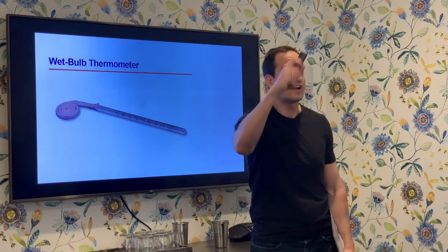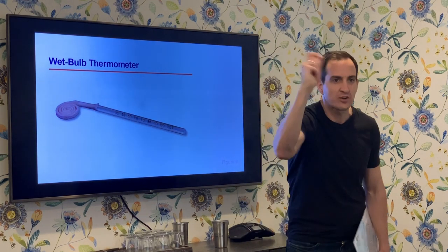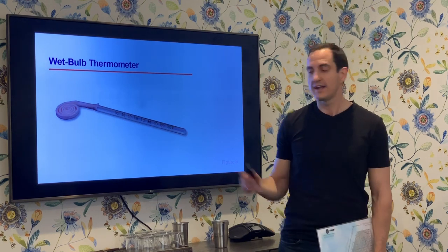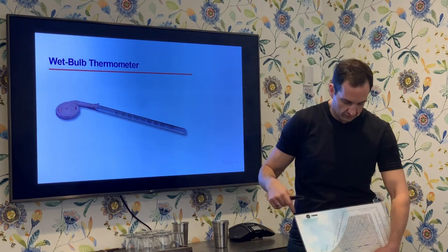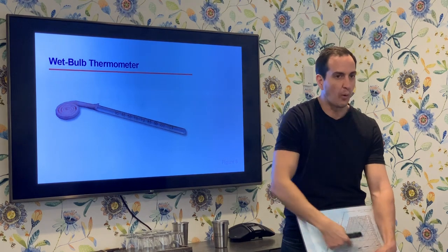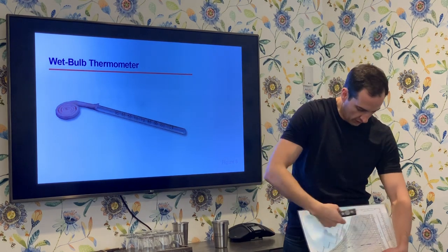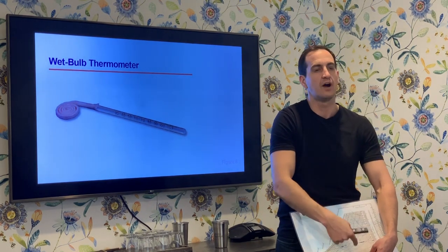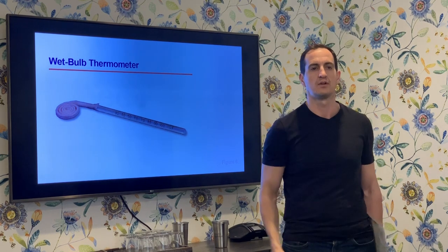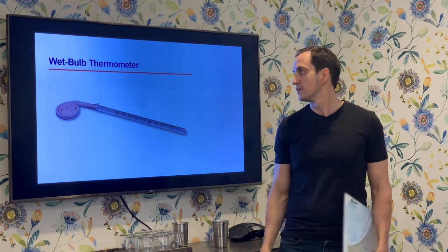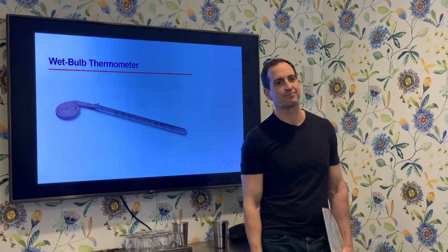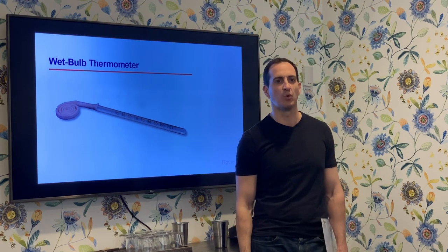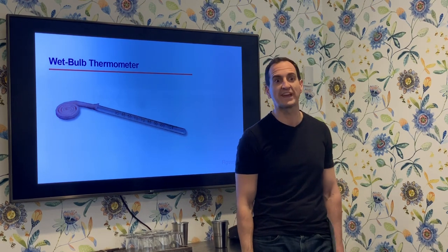To measure the wet bulb temperature, I take this wet sock and sling it around inside the room I'm trying to measure. The temperature I read will give us the second point along the wet bulb lines. Between the two points I now know where we are on the chart. That is because of the evaporative cooling effect of water — the same reason that we sweat when we get hot, and the same reason that plants transpire when exposed to radiation.